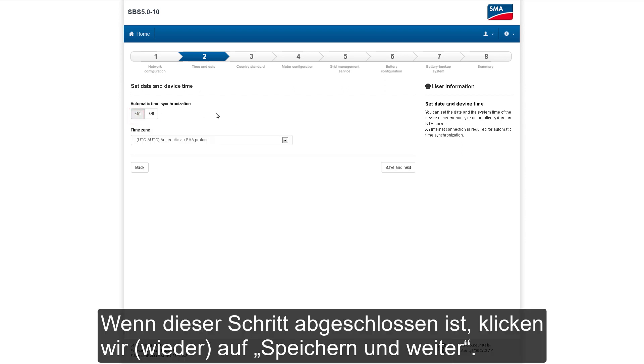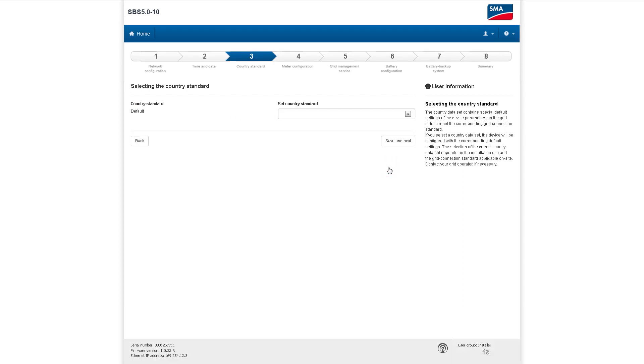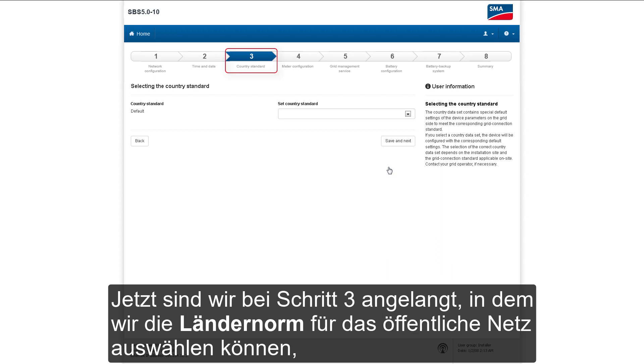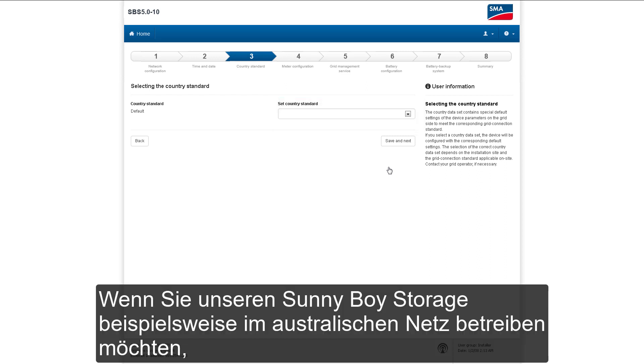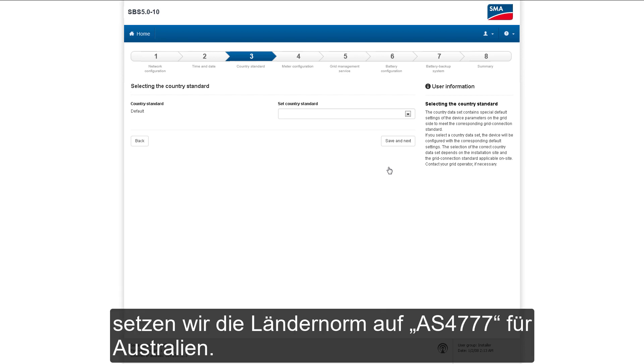After this has been finished, we click Save and Next again. Now we are at step three, where we can select the country standard of the public grid that the Sunny Boy Storage is connected to. For example, if we want to run our Sunny Boy Storage on the Australian grid, we would set the country standard to AS4777 for Australia.